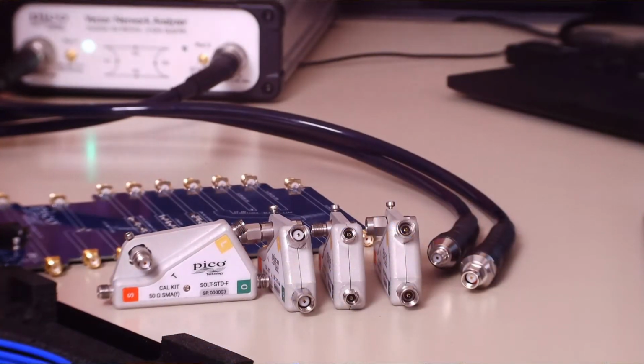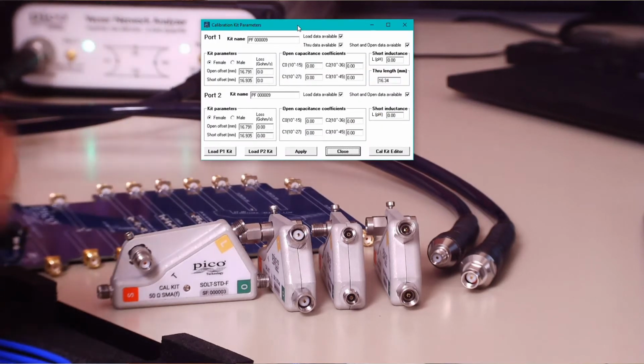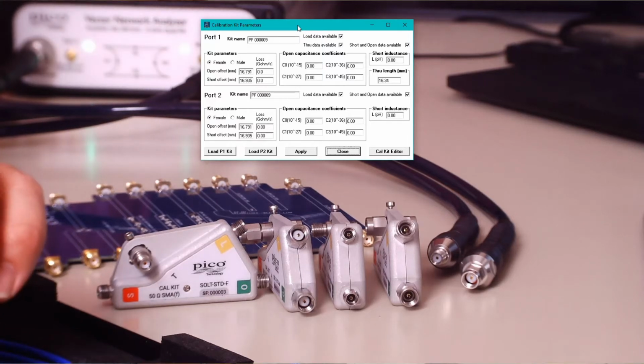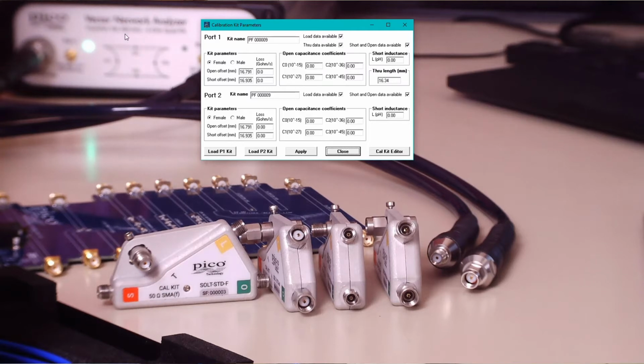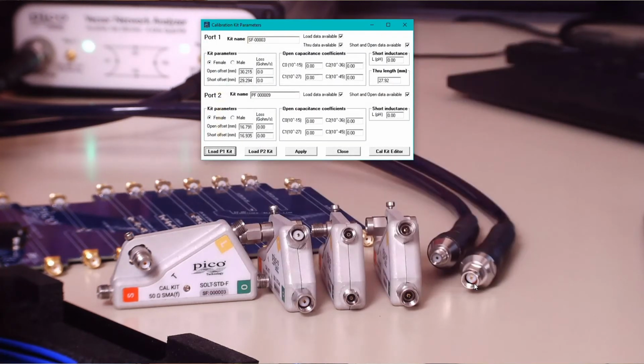Now, when we receive a calibration standard, it has a serial number, and we are all probably familiar that when we use a vector network analyzer, this user interface is of the Pico VNA, the device that you see behind here. We load to the relevant ports the cal kit that is going to be used to calibrate that port. So if I'm going to use this kit to calibrate port 1, which is that male connector there, I will need to load onto port 1 the data for that cal kit. That data in that file exactly characterizes the short, open, load and through on this cal kit.